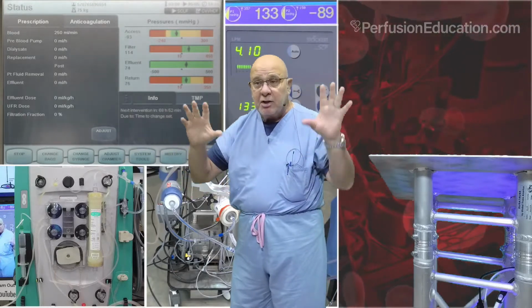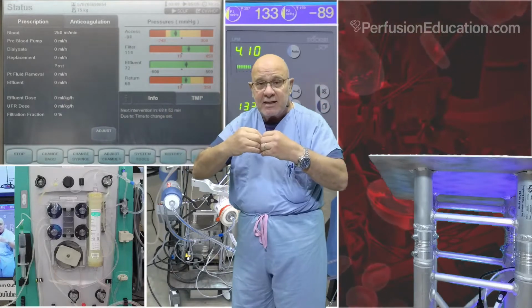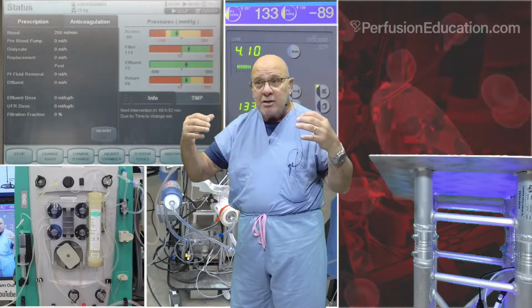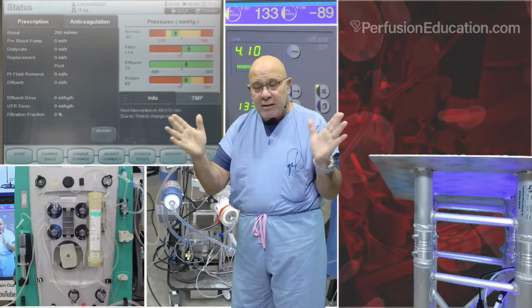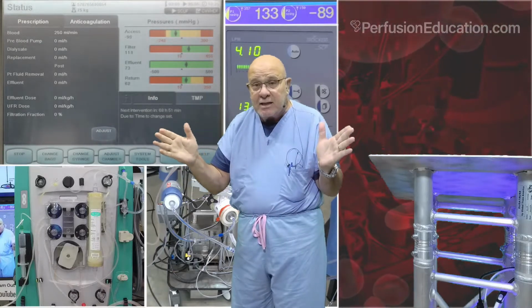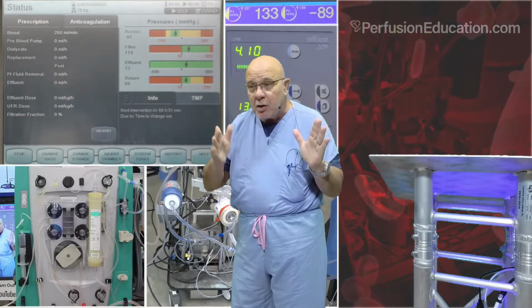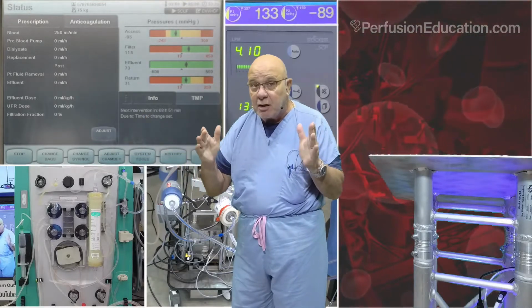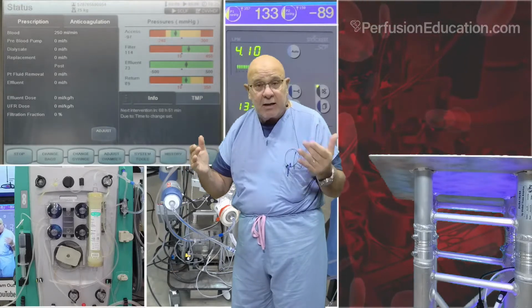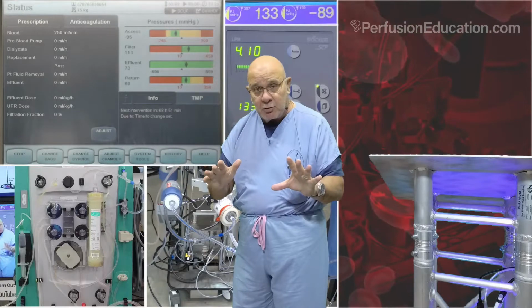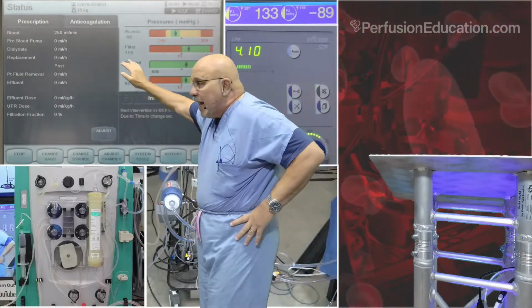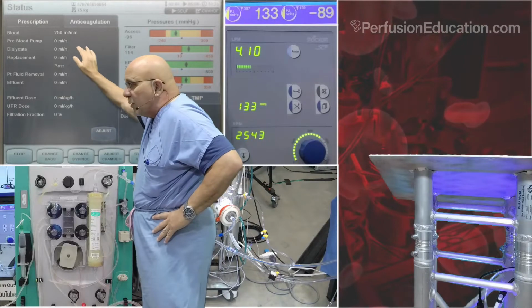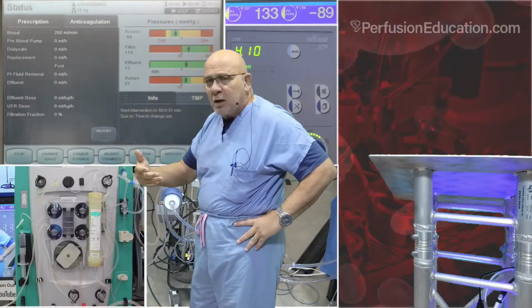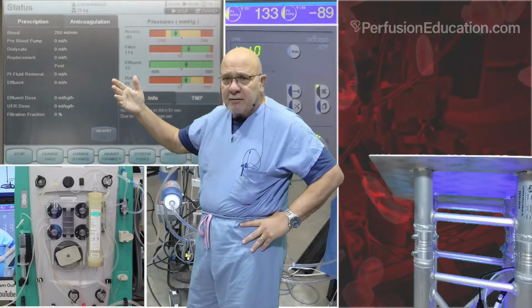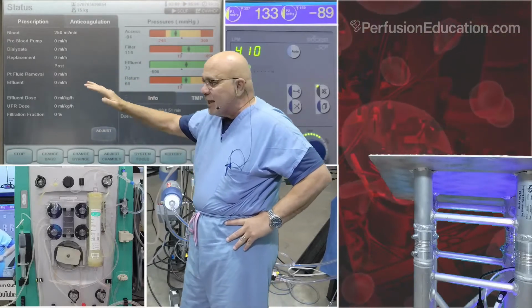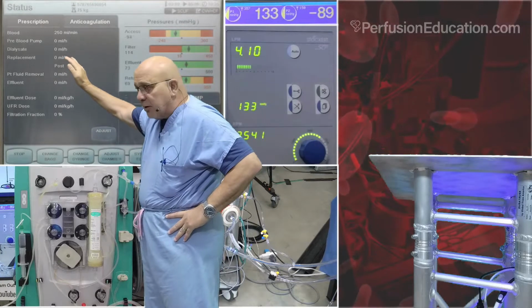Both are closed circuits, two separate closed circuits integrated together, operating together but separately. And once you understand it, it's very easy to do and you completely get it. But if you don't think it through, your CRRT treatment, again, can be very ineffective and problematic. And that's what we're trying to avoid here. But what you see is an access pressure. We're flowing 250 cc's a minute. We can flow much, much more than that. When you're on the ECMO, you want to flow about 400 if you can. But for this demonstration, that's what it would be currently if it was in a temporary dialysis catheter.